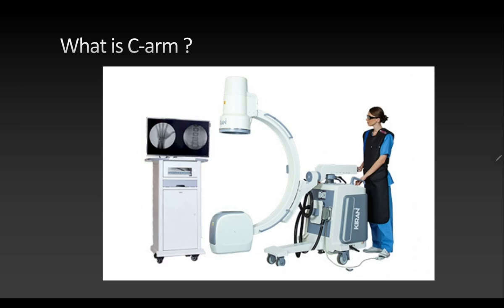The C-arm is a machine with an arm shaped like the letter C. At one end there is an x-ray generator and at the other end an x-ray detector. The advantage of the C-arm is that it emits x-rays, detects them, and projects the image onto a screen in real time. This allows surgeons to take continuous x-rays while the patient is on the table in the operating theatre. The arm can be rotated in various directions and moved to take serial x-rays of different regions.